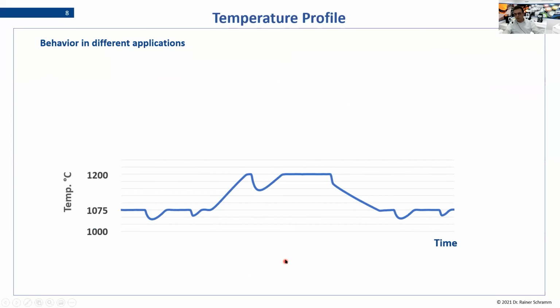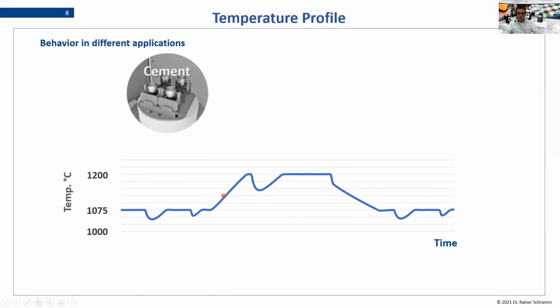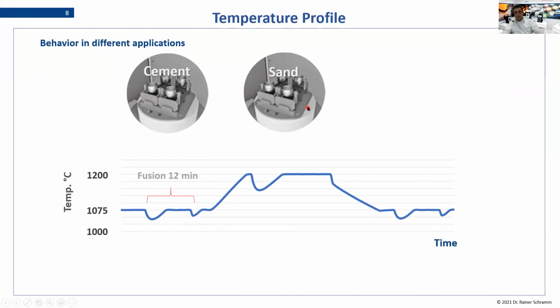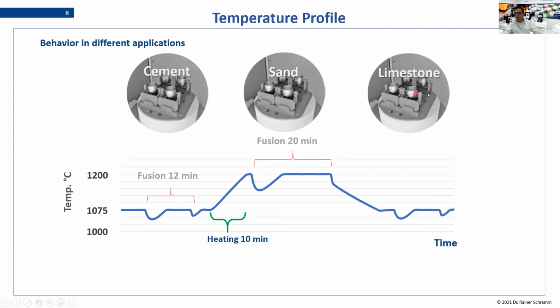But how does it behave now in different applications? Yeah? So let us assume again our cement example. So we fuse 12 minutes, 4 samples for cement. Then you say, now I want to do sand. And this means we need a higher temperature. So automatically the furnace heats up to get the conditions for sand. Then the samples are introduced. If it's pure quartz, you would probably need a fusion program of 20 minutes. And after that, if you do a limestone, you cool it down again, and you will continue with the next fusion. Yeah. So you see the system is able, fully automatic, to handle different applications, different timings, different temperatures, and this up to 4 different applications.